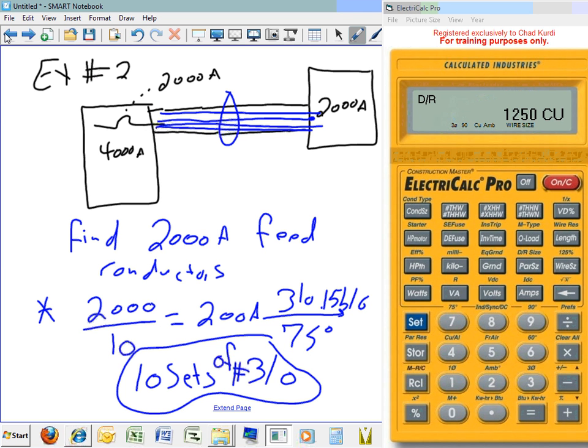But the minute that you set your mind on the panel size, these are panels. See how we move from panel to panel. The minute that you set your mind on the panel size, you match the overcurrent device when you feed it. How to get the panel size is when you start. 1.25 becomes a major part when you do branch circuit. These are feeders, feeder to feeder. You incorporate the 1.25 in the way you calculate the feeder. You're going to see it more as we go to the commercial too. Very good point.